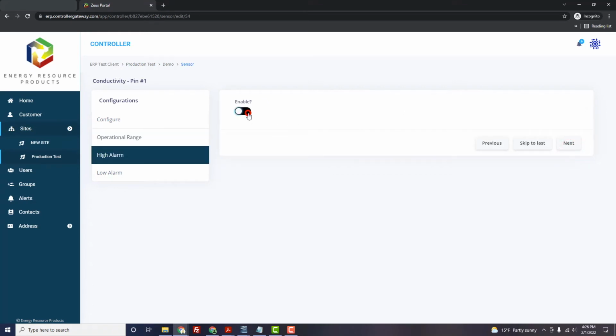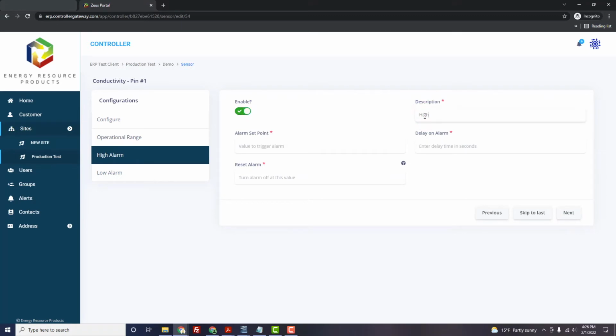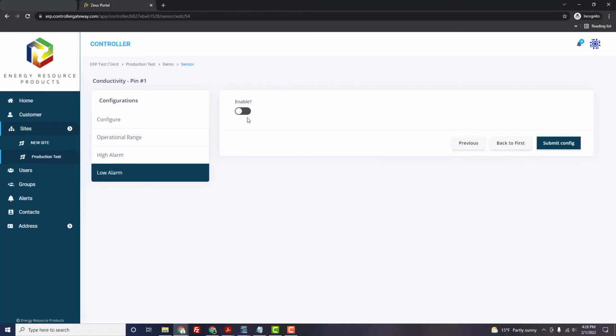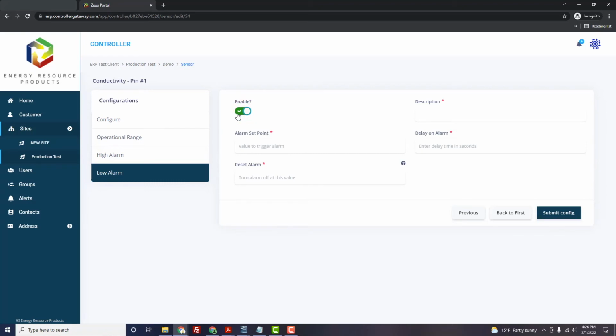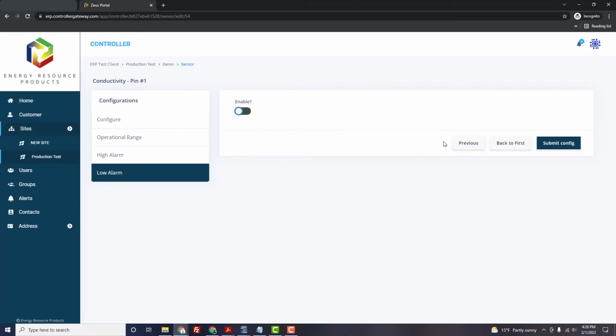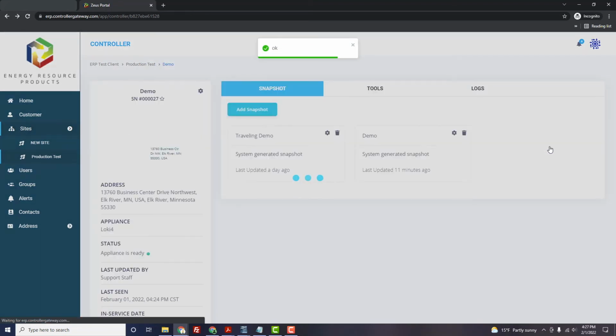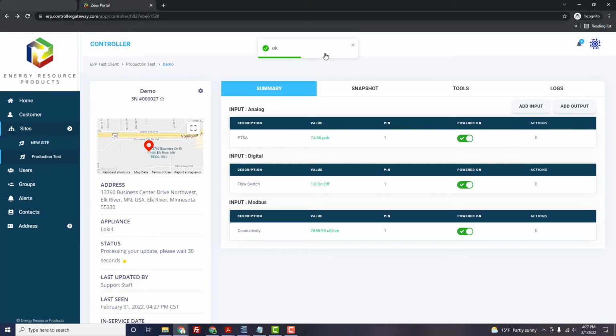Alarm may be enabled by selecting the toggle. Complete the fields. Each box contains additional text to assist in setup. Note that delay on alarm is in seconds. When finished, select Submit Configuration. This will send the configuration to the digital controller. A toaster confirms the information has been received by the digital controller.